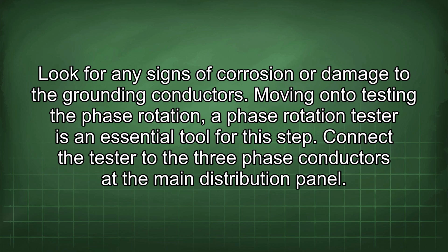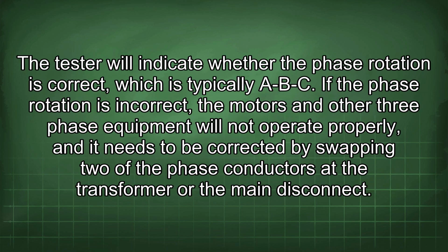Moving on to testing the phase rotation. A phase rotation tester is an essential tool for this step. Connect the tester to the three-phase conductors at the main distribution panel. The tester will indicate whether the phase rotation is correct, which is typically ABC. If the phase rotation is incorrect, the motors and other three-phase equipment will not operate properly, and it needs to be corrected by swapping two of the phase conductors at the transformer or the main disconnect.